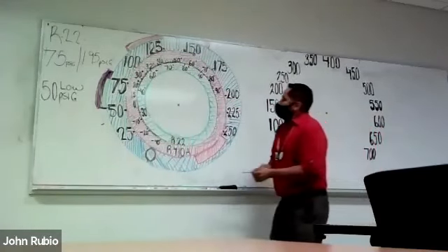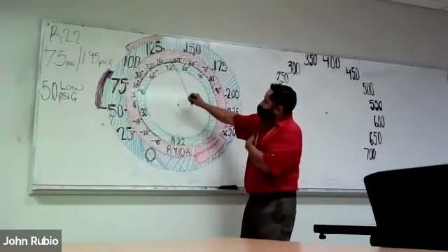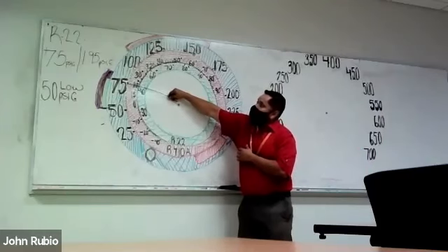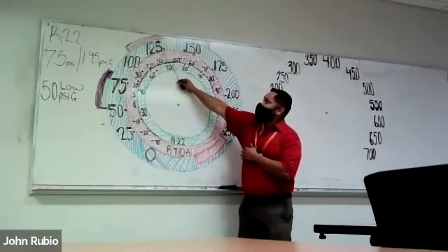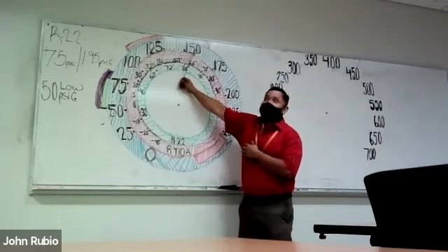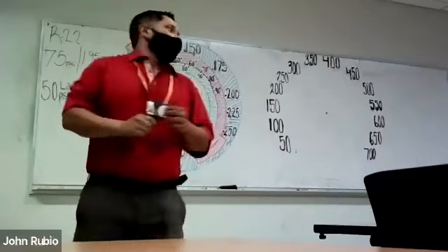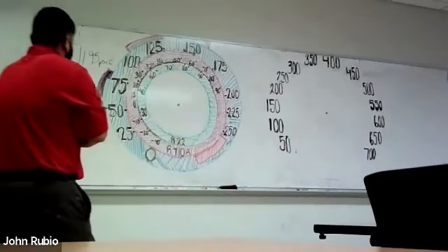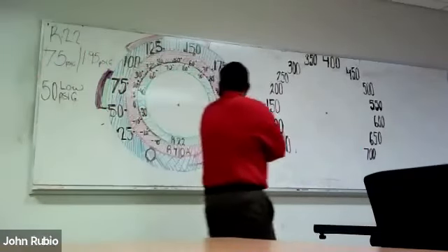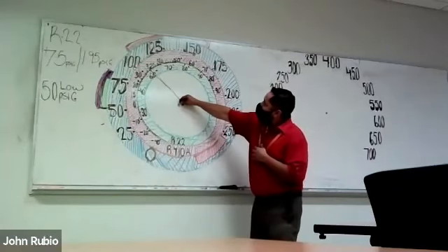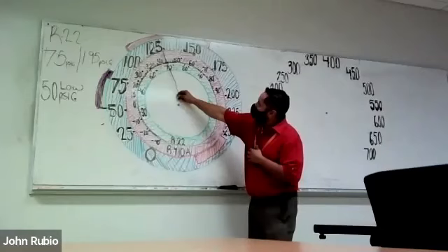So if we're at 125, we know our sweet spot for R22 is 75. Where is the sweet spot in here? There is a sweet spot in here, typically above 125, somewhere before 160. You won't find that sweet spot without superheat and subcool. When we come up to 125, there's a lot of room for improvement.